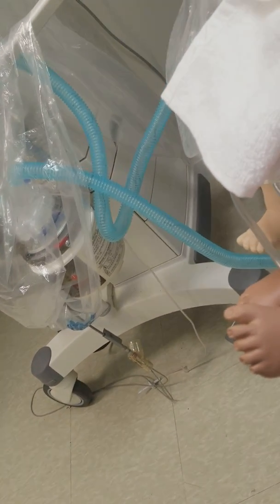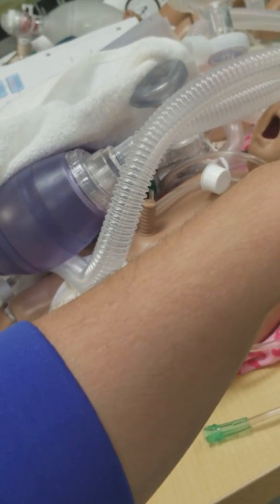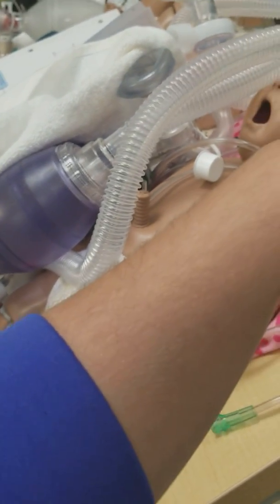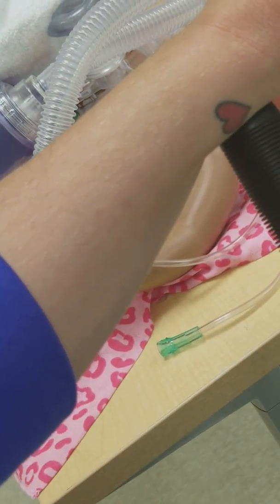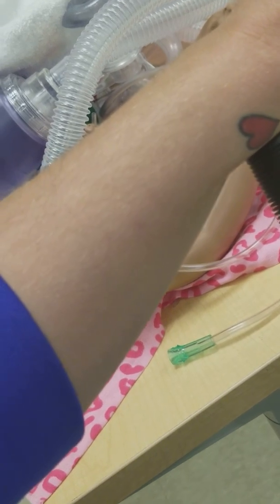As I described on Tuesday, if you have your ventilator circuit in an isolette that's warm to keep the babies warm, and the Y part of your circuit is inside and the rest of your circuit is outside, that is going to be the most infuriating part for you. You're going to have washout, rainout. So, makes sense? Temperature gradient causes rainout.